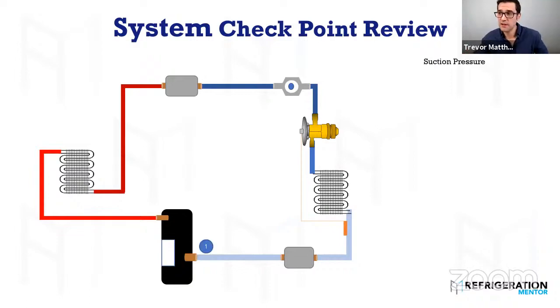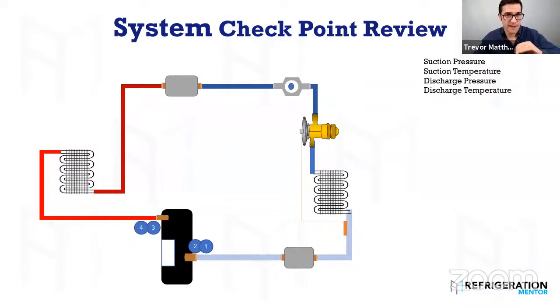Things you need to check. So suction pressure, you need to check it. Suction temperature, every time, these two, because you can get your superheat back in your compressor. Discharge pressure, discharge temperature, mandatory. Anytime you're doing troubleshooting, you need the numbers. You can't just say it's good, putting your hand on it, oh, it doesn't feel like it's burning. I was taught by a journeyman, oh, if you spit on the head and it starts to boil off, then you know it's overheating. That's not what you do. You use your gauges and tools. That's what they're for, if you want to be the best.